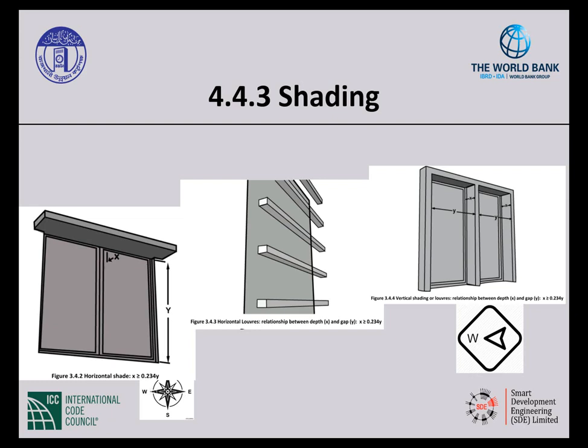All right, so 4.4.3 on shading tells us that for naturally vented buildings of all occupancies, you have to provide horizontal sunshades over the windows, but only on the windows that are south, east, and west. The depth of that sunshade is going to be the height of the window times a factor of 0.234. Right? So it's height of the window times a factor of 0.234. And this figure is directly out of the code. This is the picture taken right out of the code.